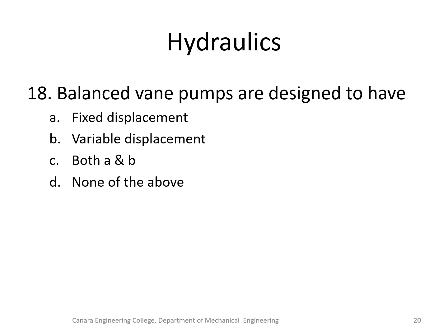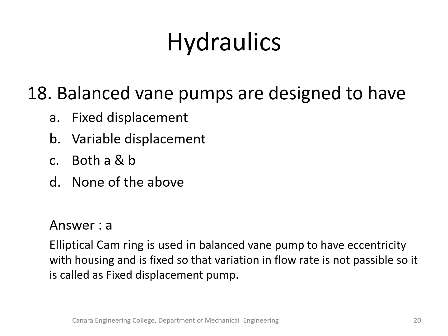Balanced vane pumps are designed to have a fixed displacement, a variable displacement, both A and B, none of the above. Answer is A, fixed displacement. Elliptical cam ring is used in a balanced vane pump to keep eccentricity with the housing fixed, so that variation in flow rate is not possible, so it is called a fixed displacement pump.